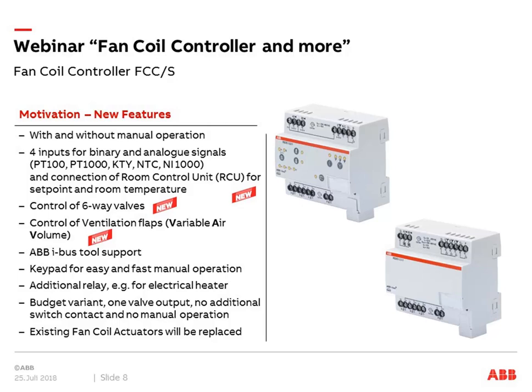If you choose a component with 0-to-10 volt and only need one output — for a two-pipe system or six-way valve control — the second 0-to-10 volt output can be used to control ventilation flaps or dampers for air handling. If you select variable air volume control, dedicated parameters and further options are available to control these components.